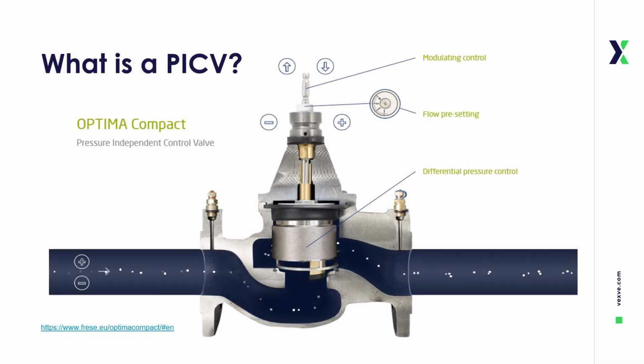A PICV, or Pressure Independent Control Valve, is a smart solution for modern hydronic systems. It combines three functions into a single valve. It works as a control valve, regulating flow precisely at all part loads between fully open and fully closed. It has an integrated differential pressure regulator, ensuring stable operation even under fluctuating pressure conditions. It works as a flow limiter, preventing overflow and ensuring that inefficiencies are always avoided. By integrating these functions, PICVs deliver constant and accurate flow control, regardless of pressure fluctuations in the system. This ensures optimal comfort, energy efficiency, and simplified system design.